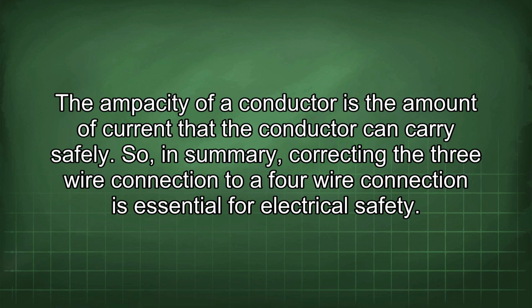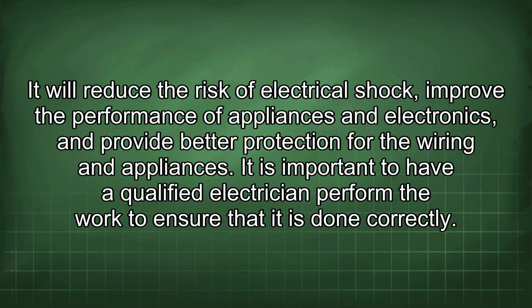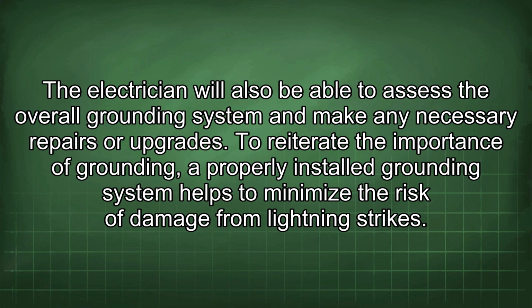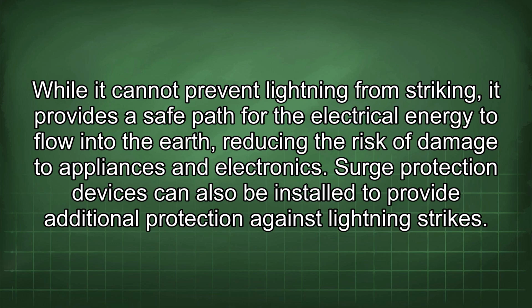So, in summary, correcting the 3-wire connection to a 4-wire connection is essential for electrical safety. It will reduce the risk of electrical shock, improve the performance of appliances and electronics, and provide better protection for the wiring and appliances. It is important to have a qualified electrician perform the work to ensure that it is done correctly. The electrician will also be able to assess the overall grounding system and make any necessary repairs or upgrades. To reiterate the importance of grounding, a properly installed grounding system helps to minimize the risk of damage from lightning strikes. While it cannot prevent lightning from striking, it provides a safe path for the electrical energy to flow into the earth, reducing the risk of damage to appliances and electronics.